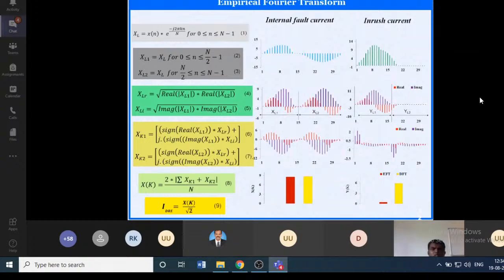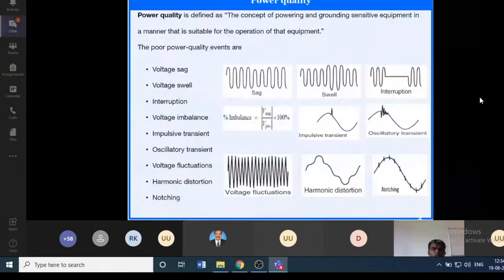Power quality is defined as the concept of powering and grounding sensitive equipment in a manner that is suitable for the operation of the equipment. Power quality events are defined as voltage sag, swell, interruption, voltage imbalance, impulsive transients, oscillatory transients, harmonic distortion, and notching. You know what is meant by sag. Sag is a decrease in the voltage level to between 0.1 and 0.9 per unit. Voltage swell is an increase in the voltage level above 1.1 per unit.